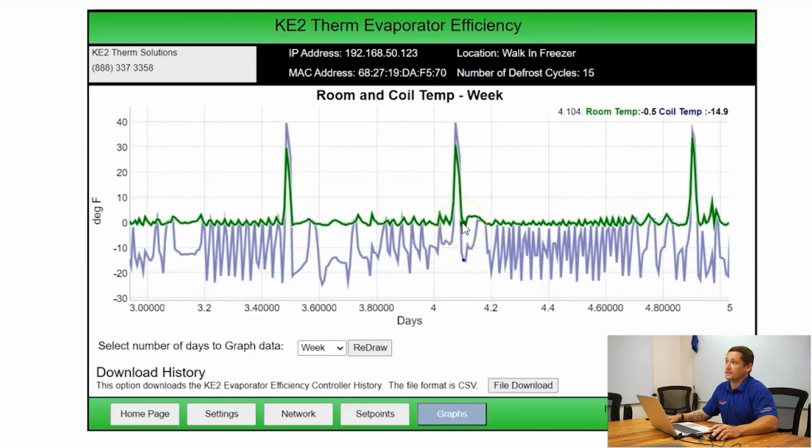And it's also going to cut down on your energy bill because you're no longer heating the full 35 to 45 minutes 4 times a day. You're only doing it about once a day, and it's just pulsing the heaters, only as needed. So that cuts down on energy. That's also going to cut down on steam in the box, building up moisture. And a lot of boxes that struggle with water building up on the roof, this is going to cut down on that as well.